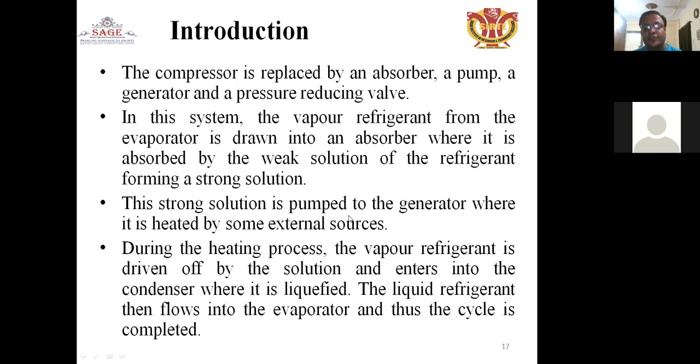This strong solution is pumped to the generator, where it is heated by some external source, such as steam that would otherwise be passed uselessly into the atmosphere. It will be used to heat this strong solution. During the heating process, the vapor refrigerant is driven off from the solution and enters the condenser, where it is liquefied.